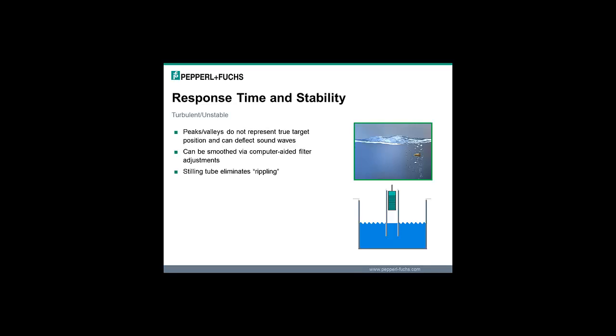There's also, through software, you can increase or decrease the amount of samplings that are taken to get a quicker response time, or if it's a very agitated tank or agitated surface, a longer sampling to smooth out an even more severe agitation. So again, we will probably in the intermediate and advanced sessions discuss how you can do that through computers. But something to keep in mind, if a sensor that's off the shelf is a little too unstable for a customer, you have the ability through software to customize the response time.